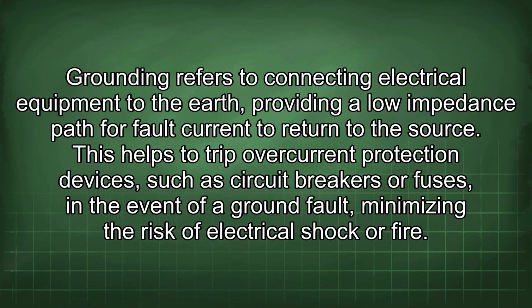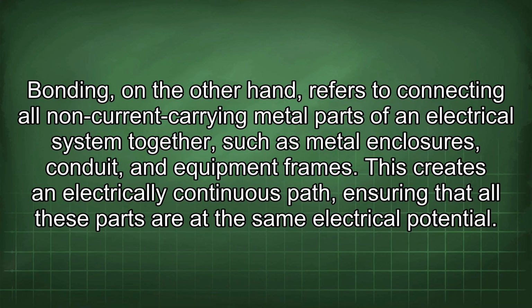Grounding refers to connecting electrical equipment to the earth, providing a low impedance path for fault current to return to the source. This helps to trip overcurrent protection devices, such as circuit breakers or fuses, in the event of a ground fault, minimizing the risk of electrical shock or fire. Bonding, on the other hand, refers to connecting all non-current carrying metal parts of an electrical system together, such as metal enclosures, conduit, and equipment frames. This creates an electrically continuous path, ensuring that all these parts are at the same electrical potential.